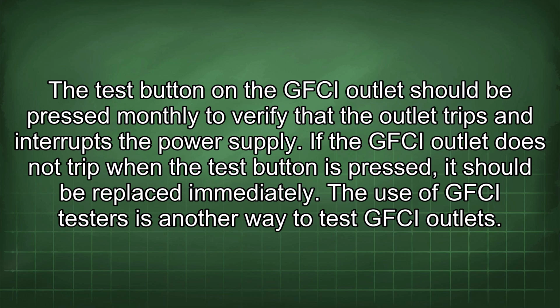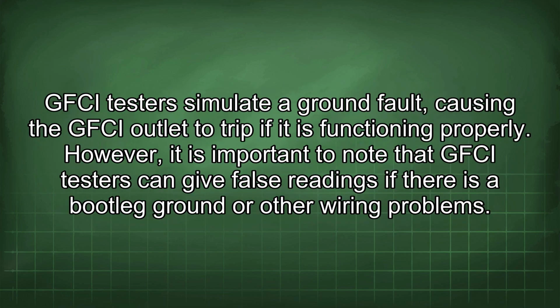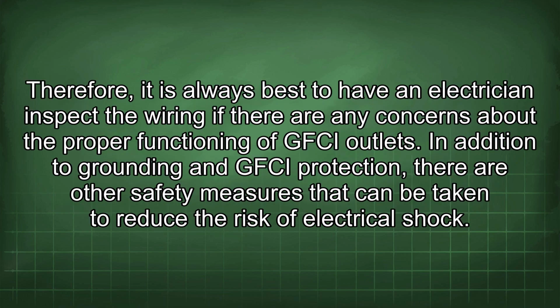The use of GFCI testers is another way to test GFCI outlets. GFCI testers simulate a ground fault, causing the GFCI outlet to trip if it is functioning properly. However, it is important to note that GFCI testers can give false readings if there is a bootleg ground or other wiring problems. Therefore, it is always best to have an electrician inspect the wiring if there are any concerns about the proper functioning of GFCI outlets.